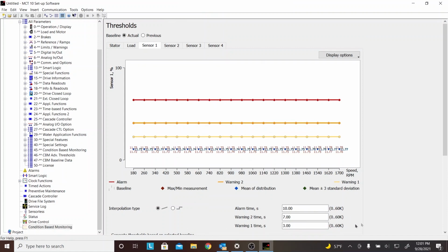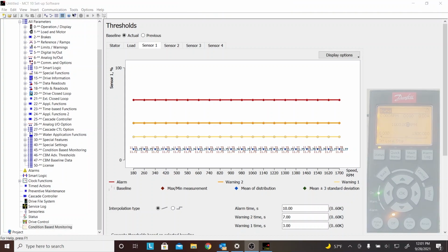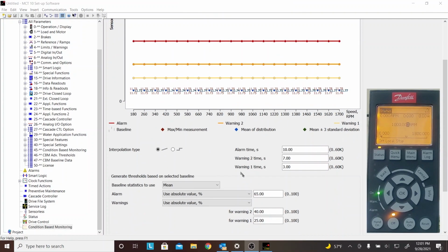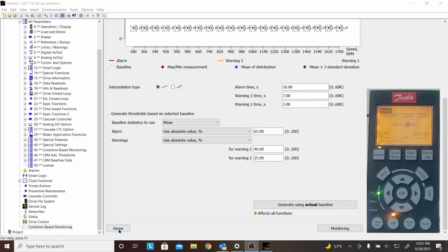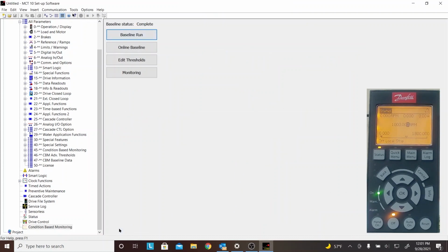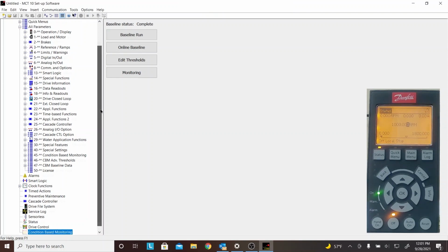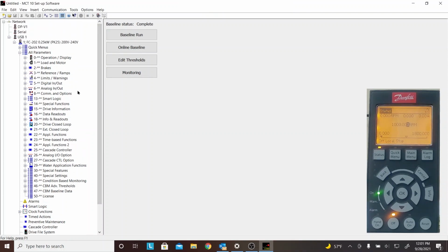I'm going to stay on the sensor, and I'm going to also bring that keypad back in. So we want to run this. We're going to go into the monitoring mode. Now we can just choose monitoring here, or we can go at home. Now I'm going to push home because I want to make a point about something. Let's say we've already done this and we've been running and monitoring the drive for a long period of time. We can easily just plug into the drive at any point in time while it's running. It's hot swappable, so you're not going to trip the drive.